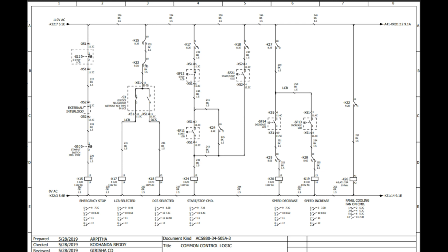110 supply will come to this place, which is another dotted box in the center of the drawing, that is the start push button. Once the start push button is pressed, 110 supply will get to K24, that is the start stop command. This is only for a fraction of a second, but to keep the system running we need a holding contact. On the right hand side of the start push button you can see K24, holding contact interlock. So the supply will continuously feed 110 volt through K24. This is the work of the holding contact, hope you know.